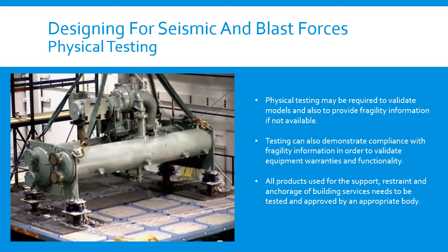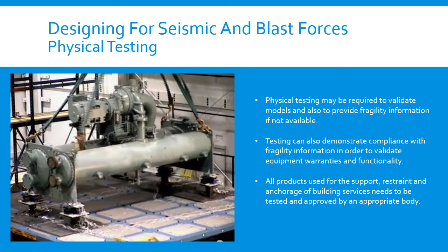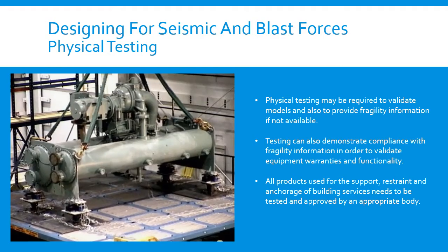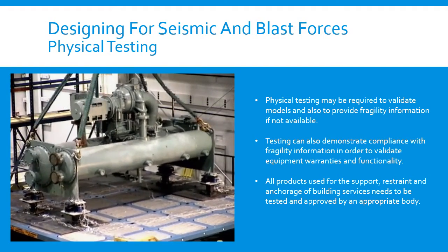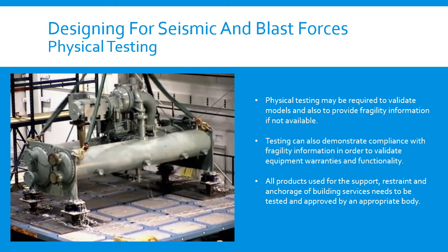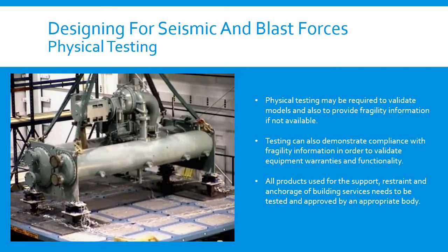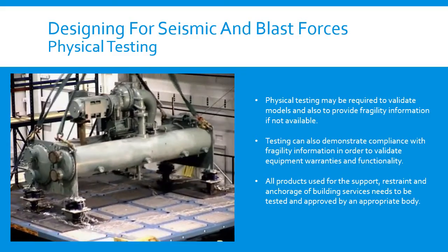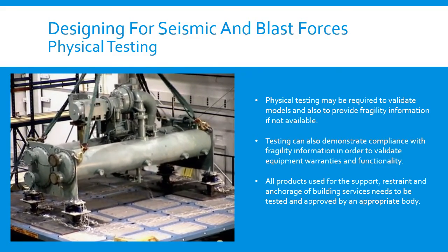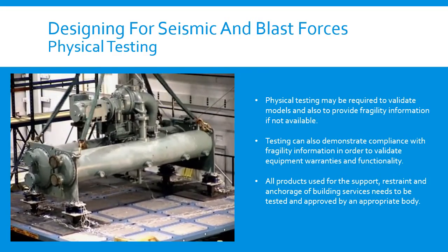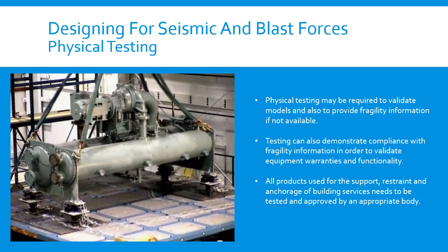Since 2000, the International Building Code has required seismic certification of all equipment required for the continued operation in an essential facility. Shaker table testing is accepted as the only method of certifying the functionality of active or energized components. Testing of equipment on isolators and snubbers is the only way to obtain certification for equipment that will need to be vibration isolated. Crucially, equipment will remain functional after an event.